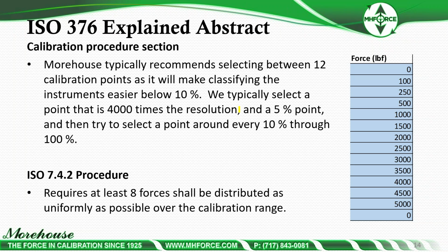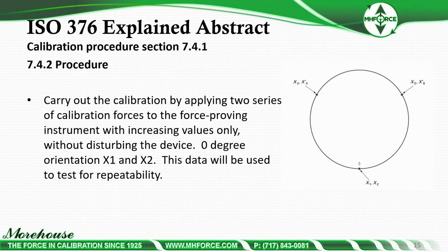ISO 7.4.2 procedure. Important to note here, I'm showing you 12. That's our recommendation because we've done a lot of these calibrations and we want to give the best possible loading range to our customers. But the actual procedure requires at least 8 forces, and they shall be distributed as uniformly as possible over the loading range. So we select our forces. And then we get to the procedure.